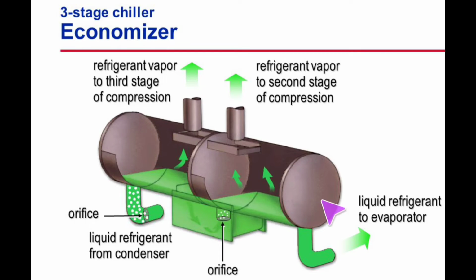And here you go. So this is the basic graphic. We're coming in first stage, come through. This gets pulled out into the third stage impeller. We go through this kind of bottom chamber here through another orifice into the second stage of the economizer, which gets pulled into the second stage impeller, and then back out to the evaporator.